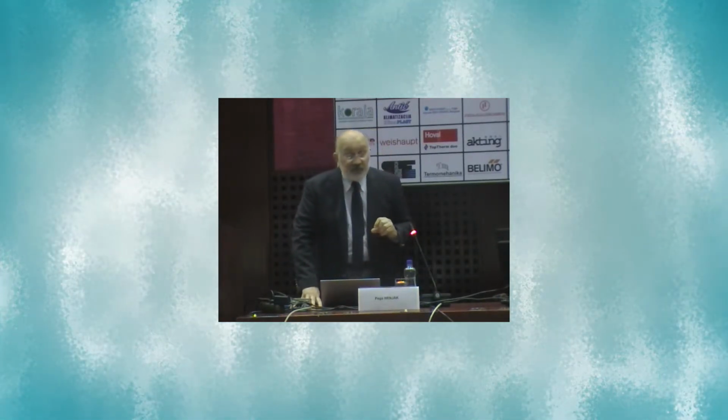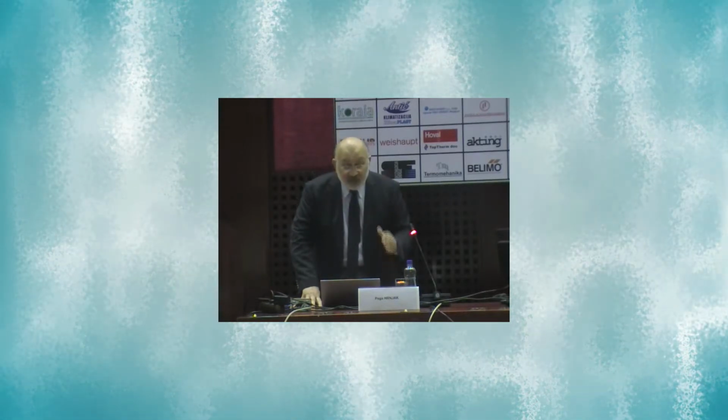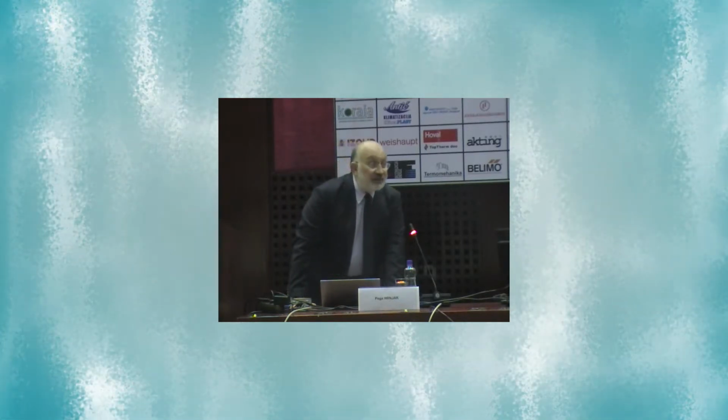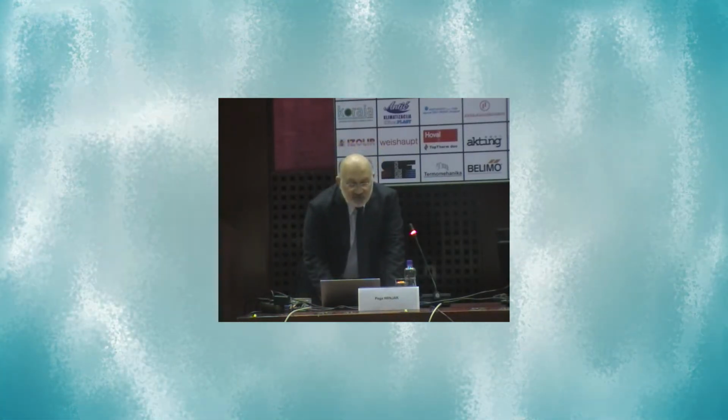Now, this is comparison of smooth versus microfin tube, that axially grooved, in heat transfer and horizontal pressure drop. For the same conditions, this here blue is mass flux of 100 kilograms per meter square per second, and then 180. The same thing with microfins. So if we compare red to red, this is the same condition, different geometry. Heat transfer coefficient is that much higher, pressure drop is that much higher.